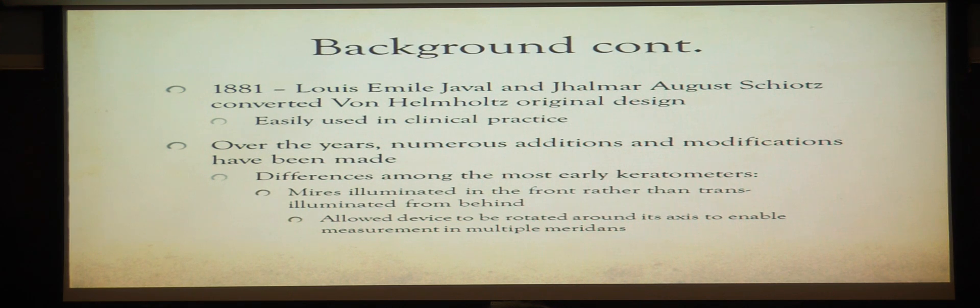In 1881, Louis Emile Javal and August Schiotz took the original Von Helmholtz device, which was primarily used in laboratories, and they modified it so that it can be more easily used in clinical practices. Over the years, a number of modifications and additions were made to the keratometer. Some of the differences between the modified keratometer and the early keratometer is that the mires were illuminated in the front rather than illuminated in the back, and this allowed for the device to be rotated around its axis and enable measurement in multiple meridians.